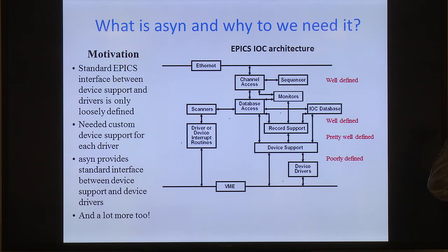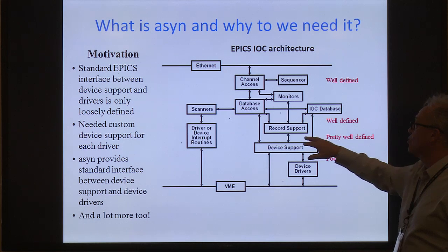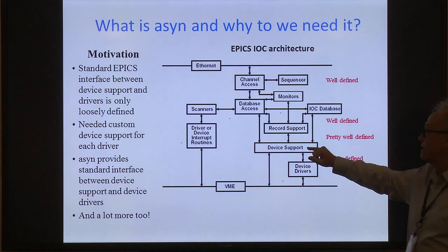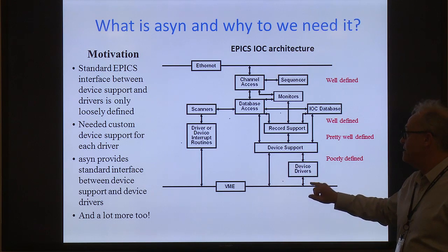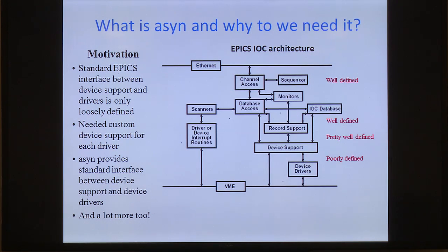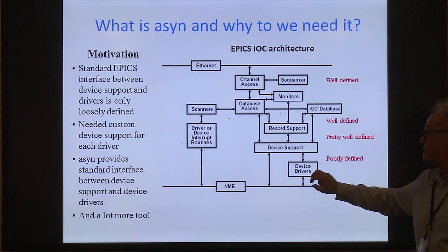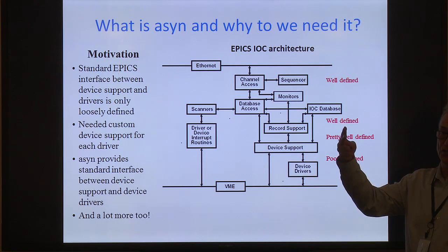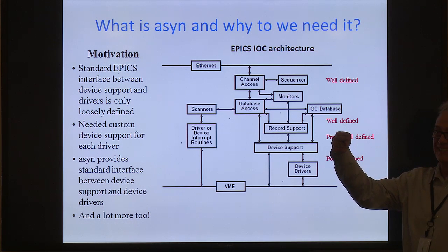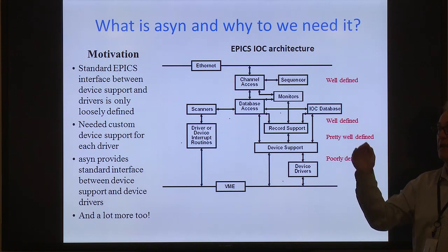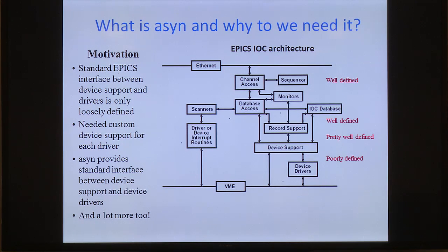Initialize, report, write or do the I/O, that kind of thing. So this is quite well defined. The problem is that the next level down, the interface between device support and a device driver, is very poorly defined in EPICS base. There is a function table that a device is supposed to provide, but it has two functions, initialize and report.